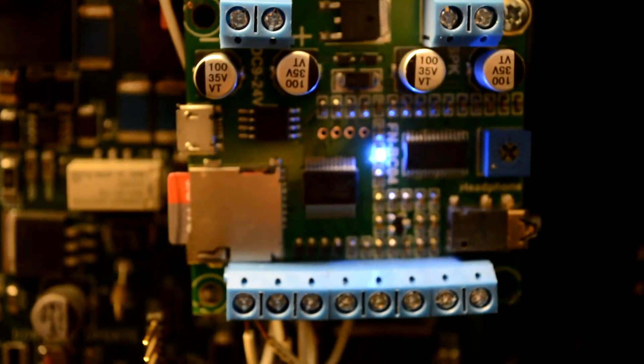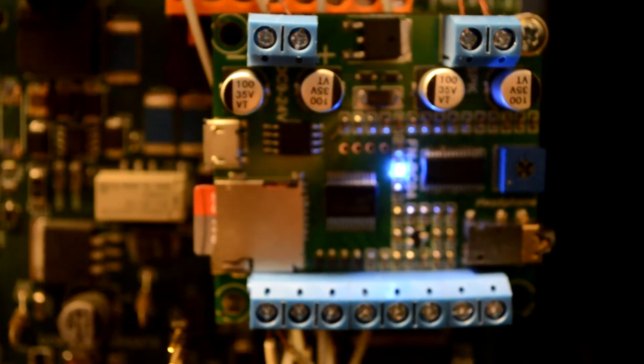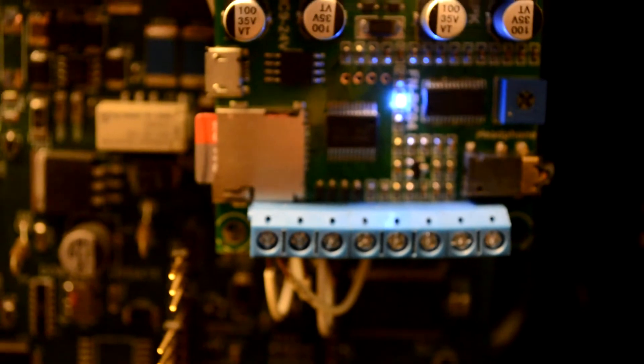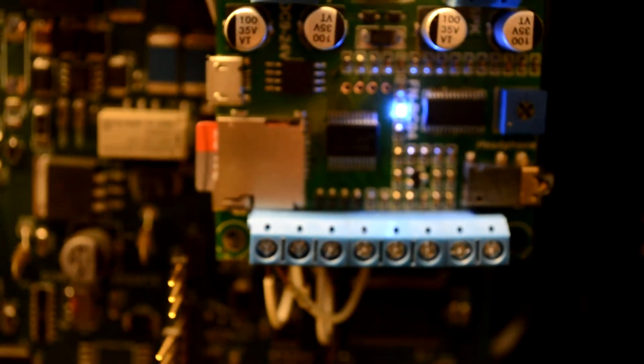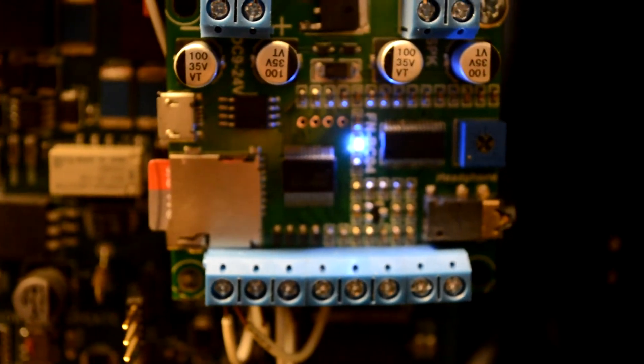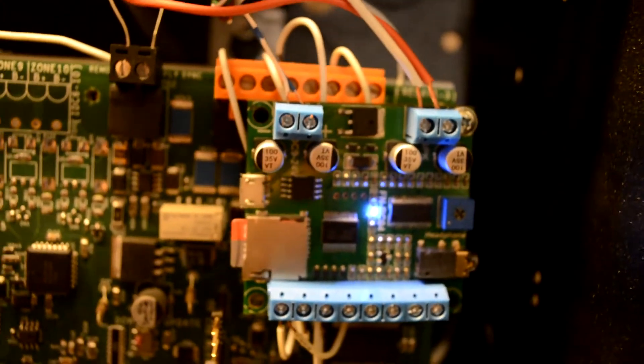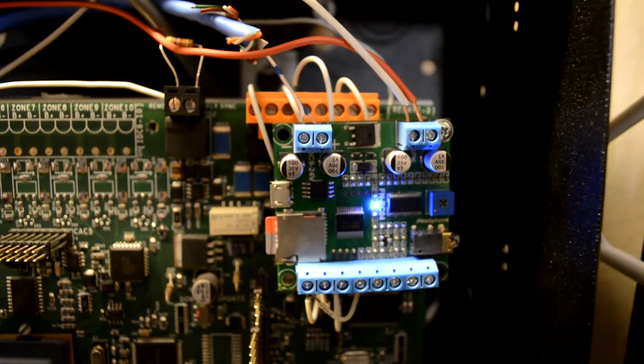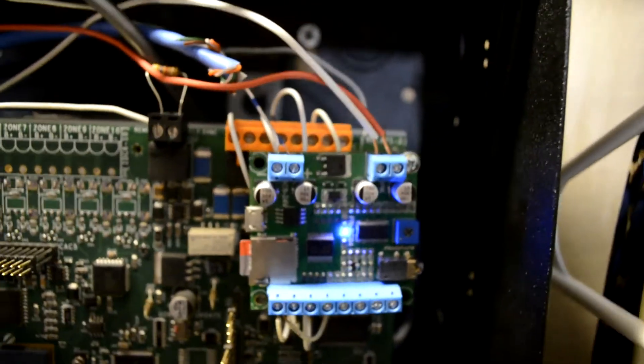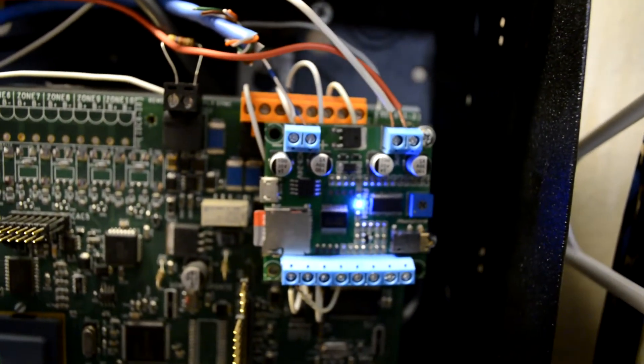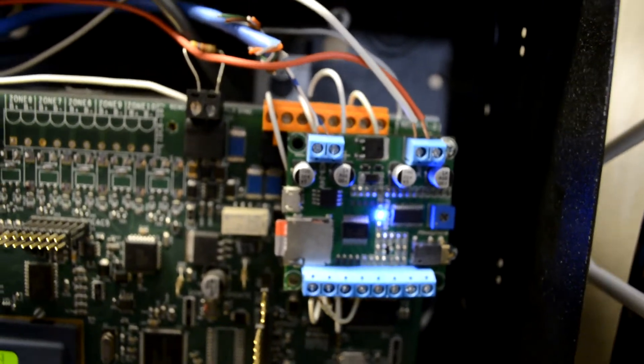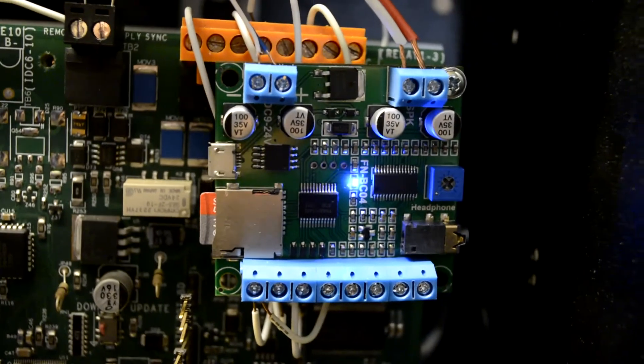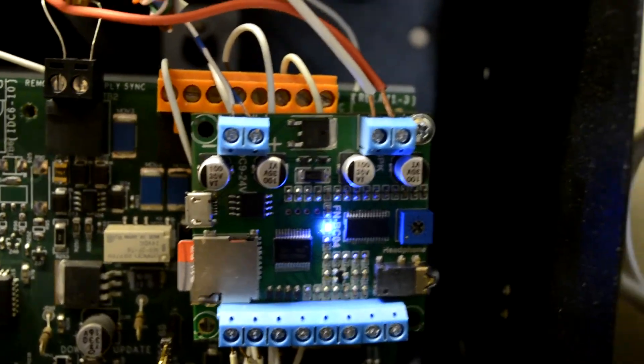Relay 2 is a supervisory relay, which I have wired to Trigger 2, and on that one I have the MP3 file 0002, which corresponds to an all-clear message. We'll be using that a little bit later. We'll have to manually trip a supervisory zone to get that to work, just because I don't have the equipment set up to use like a key switch or anything like that. We will have to reset the panel because I don't have the zone set as a temporary supervisory.